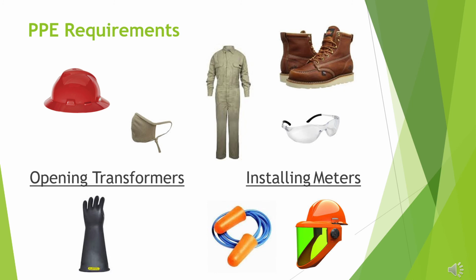So when we're looking at the CALT's PPE requirements when working around exposed electrical circuits within the arc flash boundary, we need to, at all times within the 10 feet, be wearing the hard hat, the leather work boots, the FR coveralls, and the glasses. And now with the COVID pandemic and the requirement for wearing a surgical mask at all times, you will need to take off the standard surgical mask and replace it within the 10 feet with the arc rated surgical mask.